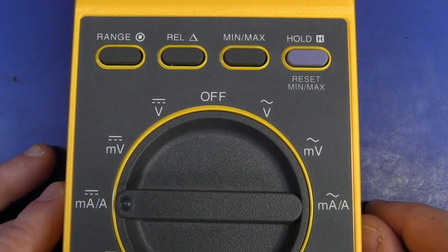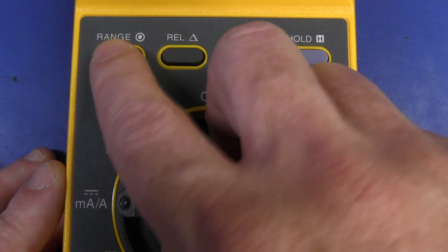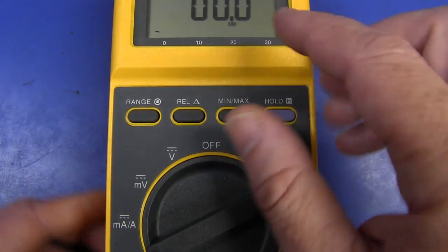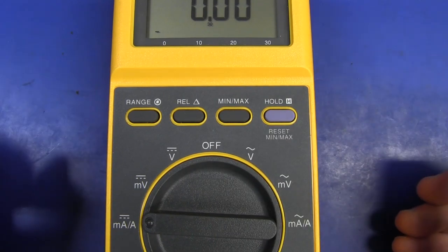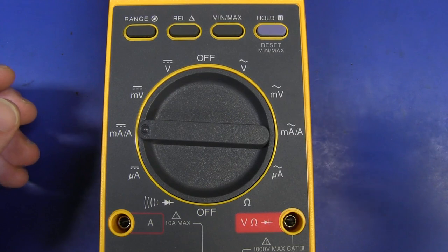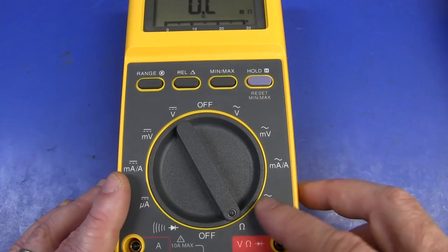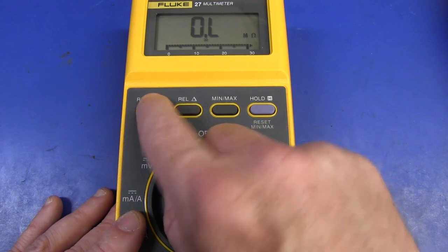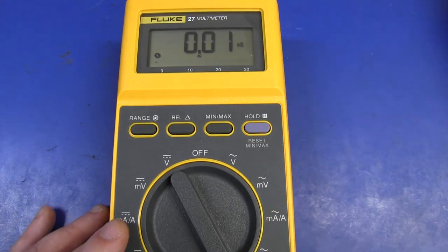Functionality-wise it doesn't have a huge amount — it's just got standard min-max, the Fluke touch hold, relative mode, and range hold. There's no capacitance, as capacitance wasn't around on multimeters when this thing was designed. But it does have a fast-updating bar graph display down to a couple hundred milliseconds. If you just want a super reliable, super rugged multimeter to measure traditional volts, ohms, and amps, this one's hard to beat. On the ohms range it does have conductance or nano Siemens — just press the range button twice to put it into nano Siemens, great for measuring leakage.